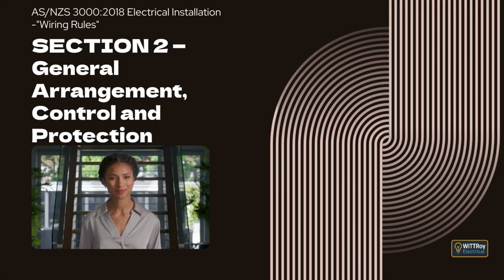Normally, we do not isolate the neutral conductor of a consumer main, or a neutral that is also used as a combined protective earthing and neutral conductor. But there are some cases where the neutral may be switched, such as a multi-pole device that switches all poles together, or a device that ensures the neutral cannot remain open when the actives are closed.